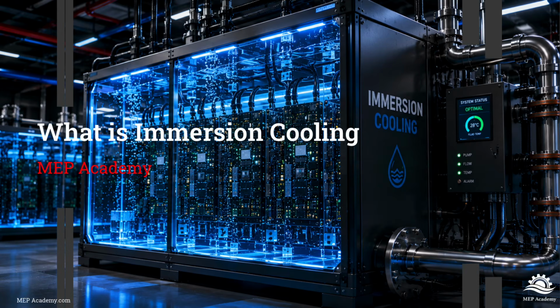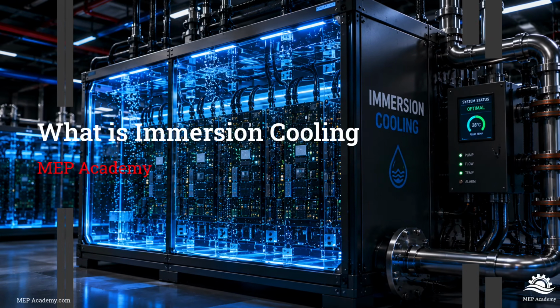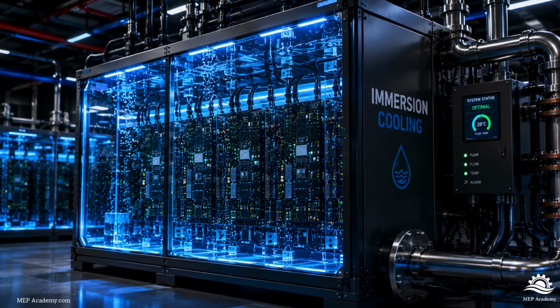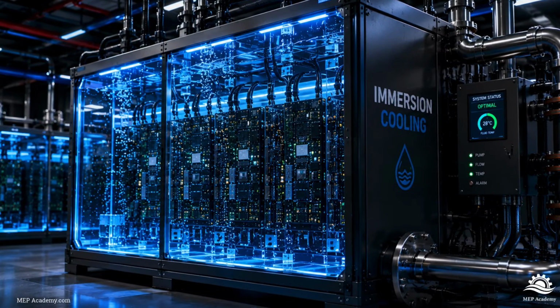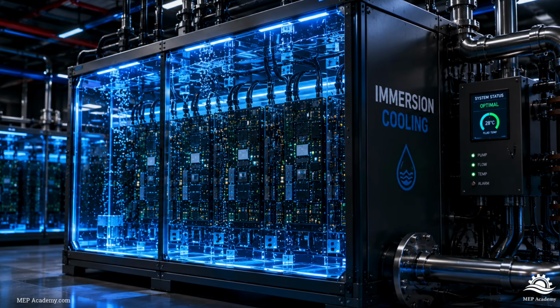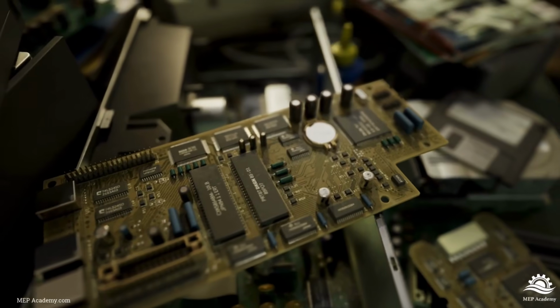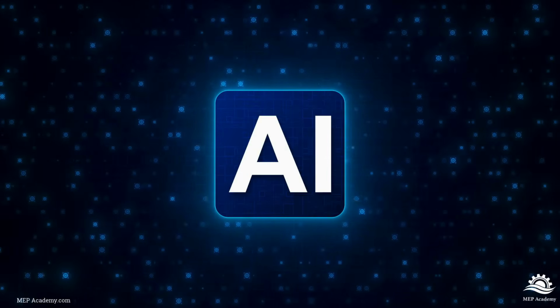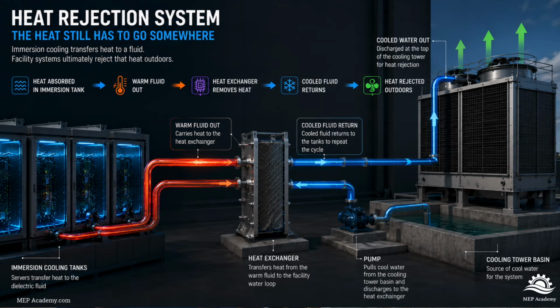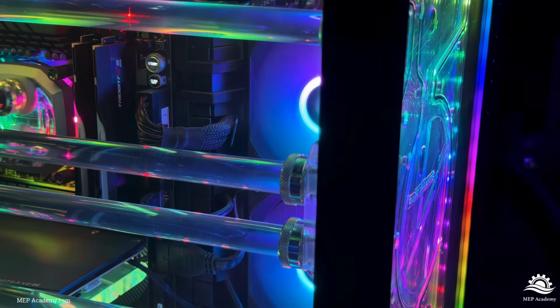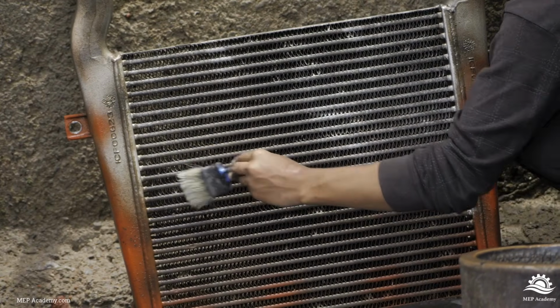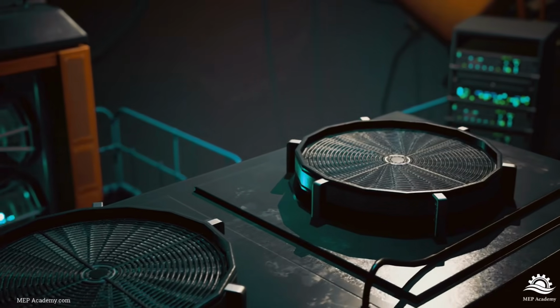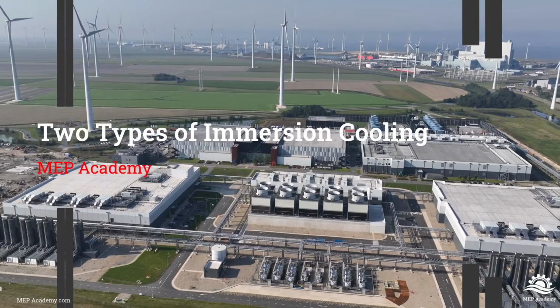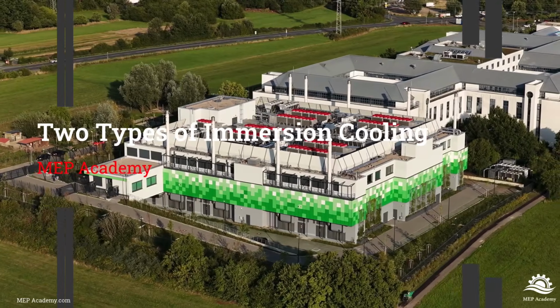Immersion cooling is exactly what it sounds like. Instead of cooling the room, you cool the servers directly. The servers are installed inside specially designed tanks filled with a non-conductive dielectric fluid. Dielectric simply means electricity cannot flow through it. The liquid safely surrounds all of the electronic components without causing short circuits. As the processors generate heat, that heat transfers directly into the liquid. The warmed liquid then travels through a heat exchanger where the heat is removed before the fluid returns back to the tank. Then the cycle repeats over and over again. Think of it like placing a car radiator directly around the entire server instead of trying to cool it with room air.